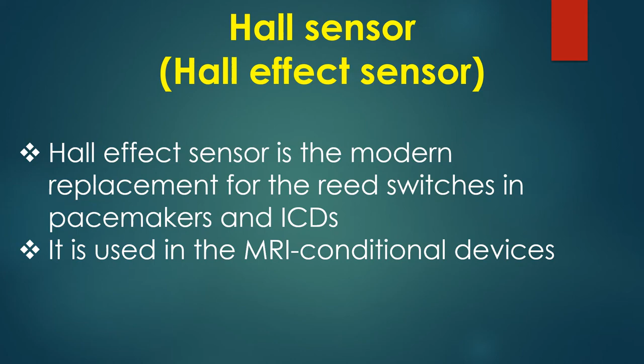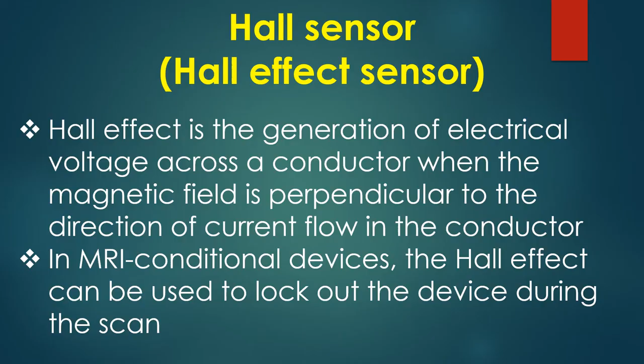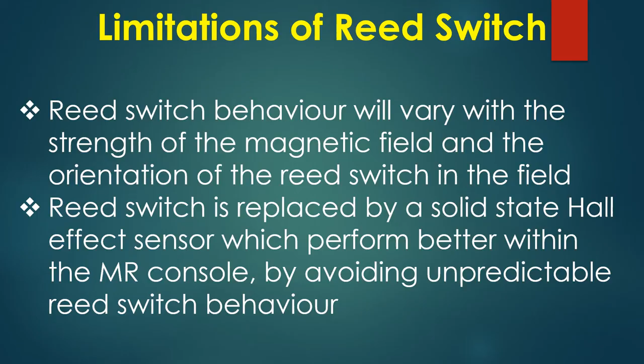Hall effect is a generation of electrical voltage across a conductor when the magnetic field is perpendicular to the direction of current flow in the conductor. In MRI conditional devices, the Hall effect can be used to lock out the device during the scan. Limitations of reed switch: reed switch behavior will vary with the strength of the magnetic field and the orientation of the reed switch in the field. Reed switch is replaced by a solid state Hall effect sensor which performs better within the MR console by avoiding unpredictable reed switch behavior.